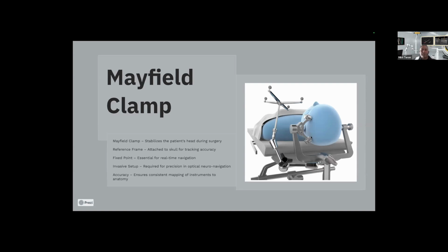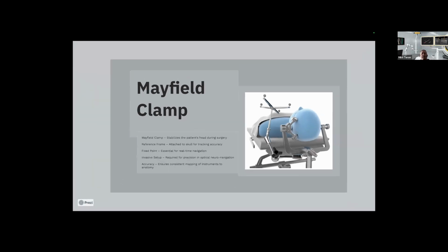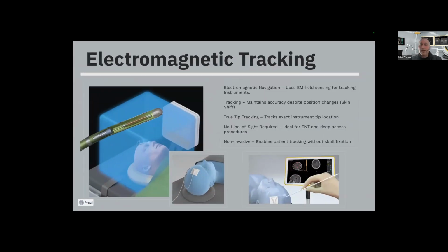And remember the line of sight. So the next technology we have then is this electromagnetic tracking. And in the electromagnetic tracking environment, the camera goes away. And what happens now is that we bring an electromagnetic field sensor into the surgical field. And this creates a 50 by 50 by 50 centimeter electromagnetic field in which it can track distortions to the field. Into that field, we send in then instruments with tiny coils wired into their tips. So it's a true tip tracking technology as opposed to a geometry tracking technology with our reflective spheres.